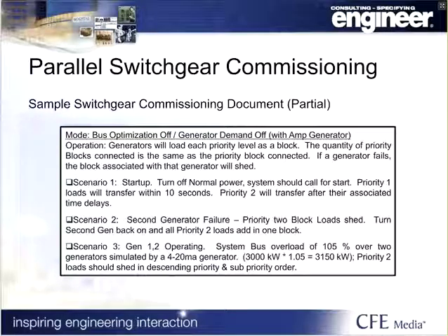So what you have the capabilities of doing in most of the parallel switchgears and most of the generator controls is simulating a load. It might be through a PLC, or it might be through a milliamp generator that they can tie into the terminals of a PLC. And you can simulate loads. I wouldn't suggest that anybody hook up a load bank that's going to overload a system to test it. That certainly would be dangerous. But you can simulate it through the PLC logic by basically simulating a load.